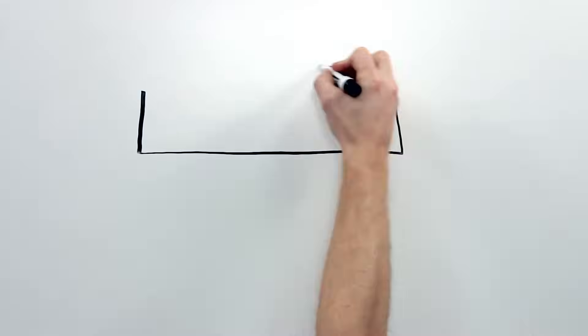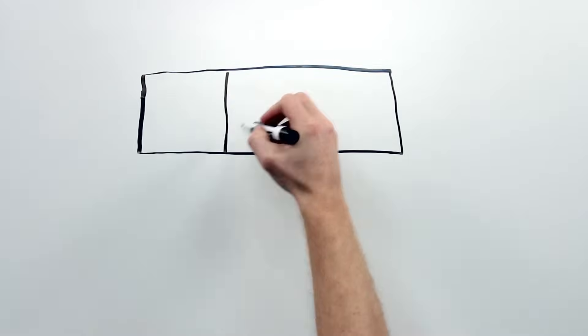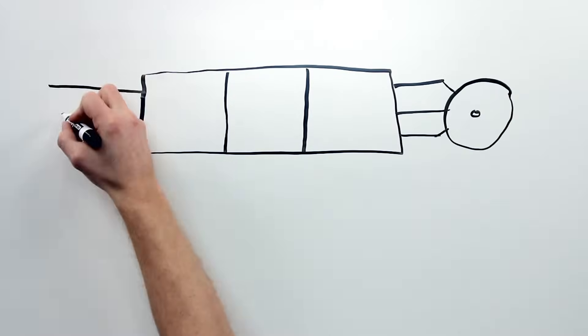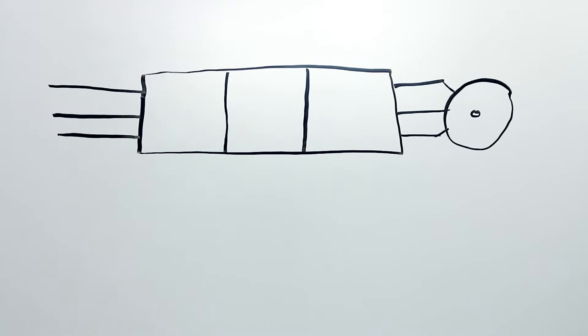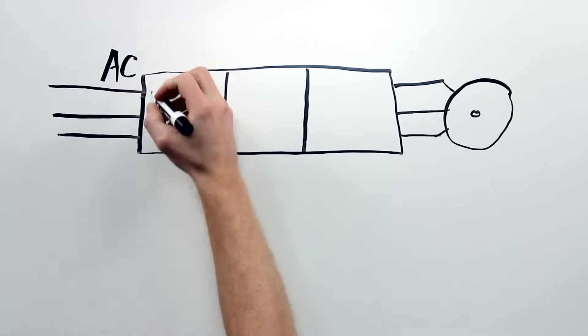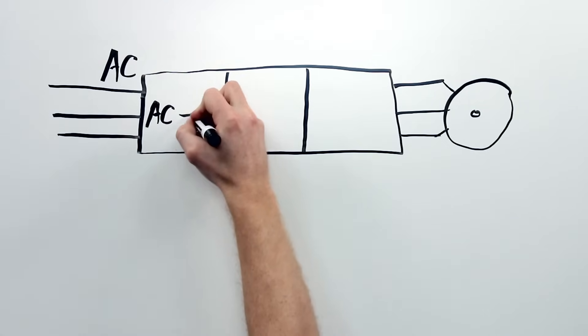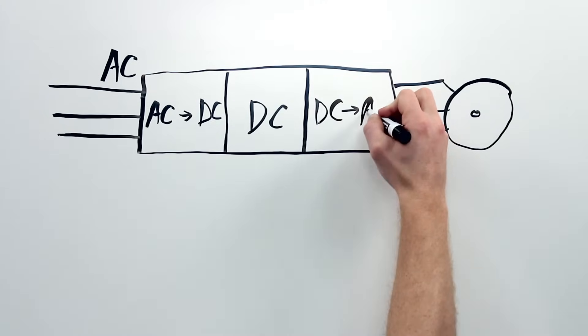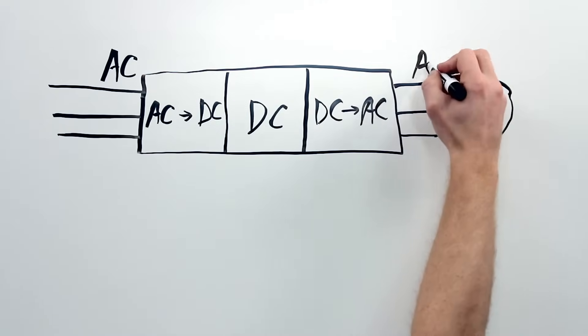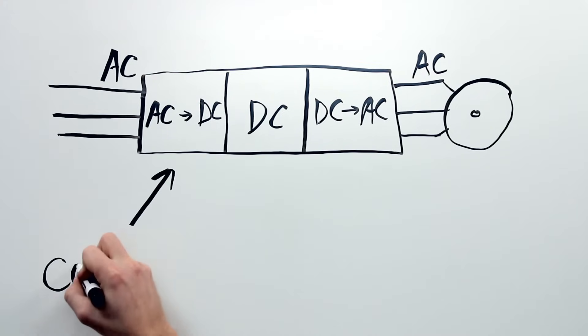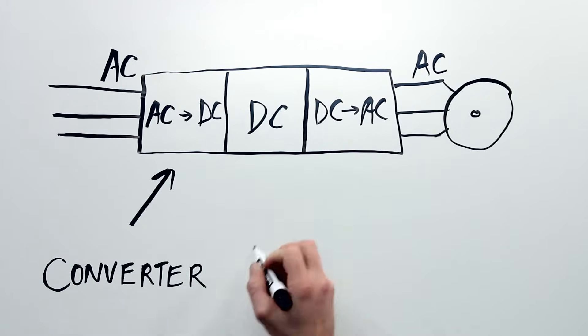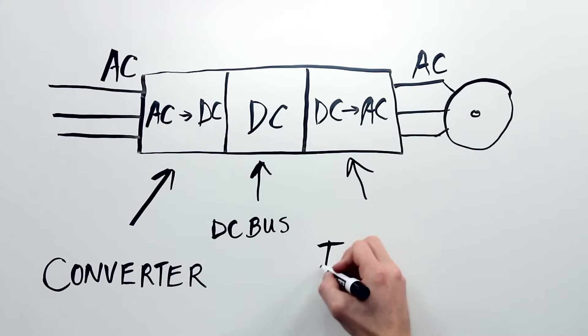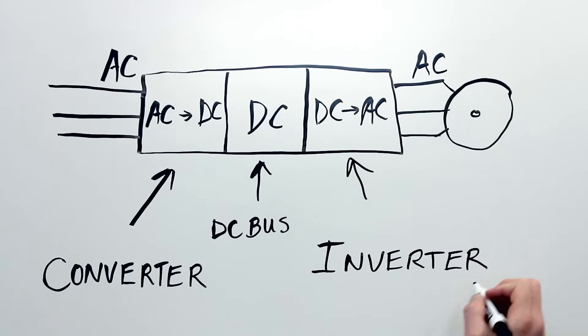Inside of a drive, it can be broken up into three main parts. The AC power from the utility enters the drive and is converted from AC into DC. Then the DC is carried over and converted from DC back into AC. These three parts are called the converter section, the DC bus, and the inverter section.